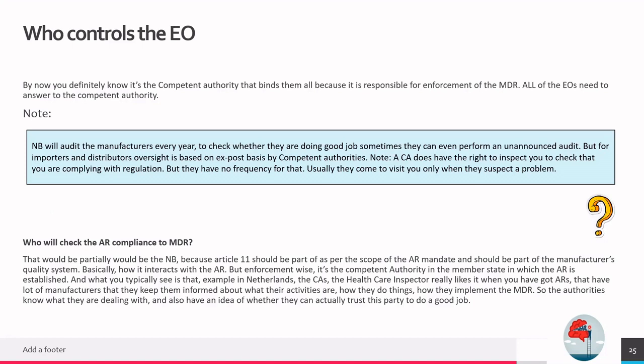That's how the system of the MDR is set up, except when these are entities that are included in the scope of the manufacturer's quality system. That is what I'm saying. If all these activities are done under the umbrella of the manufacturer, then the interlinking challenge will not be there, because they will be in one single quality management system. So common roles and responsibilities can be made into separate common processes. So it becomes easy for big companies to do that.